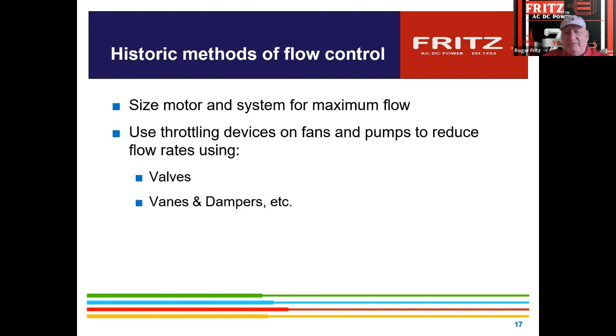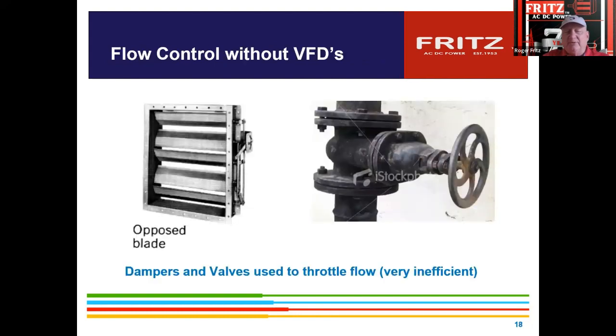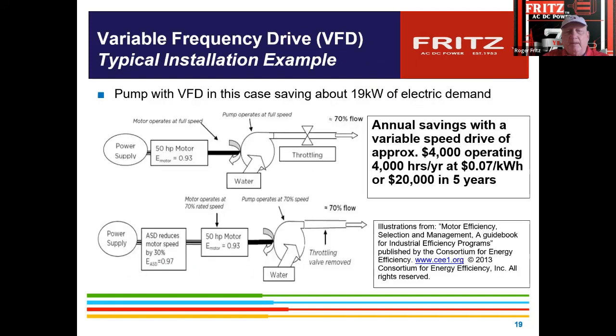So they were controlling it by vanes, dampers. That's the typical regulation valves in a building. This was the typical way of throttling on the output of the water pump, where now they open up the valving and then control it with a VFD on a 50 horsepower motor. So it does have a very big impact on total power requirement.